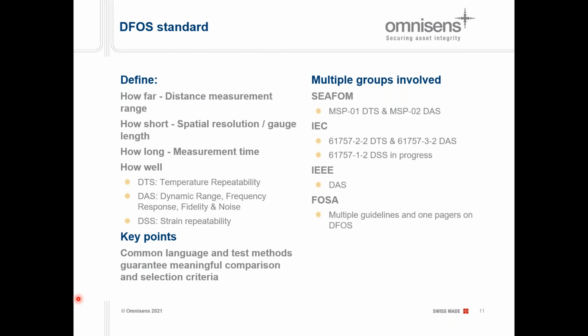How short. We have the how long, which is the measurement time, and obviously what everybody's interested in, which is the how well. For temperature, that is usually translated into repeatability. For acoustic, it's more the dynamic range and the noise, and for strain, it's the repeatability as well. I think the key point in the standard is that it brings a common language and common test methods, so that eventually, when you compare performances and look at different instruments, you can really compare things which are comparable. There are multiple groups involved in this.